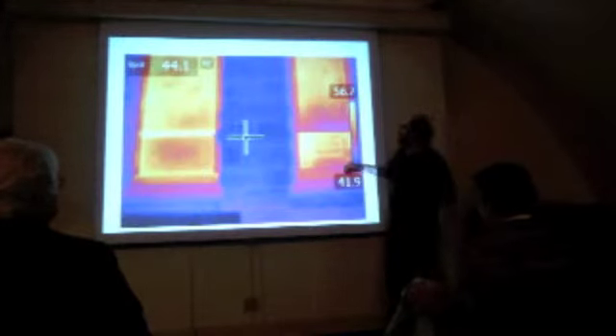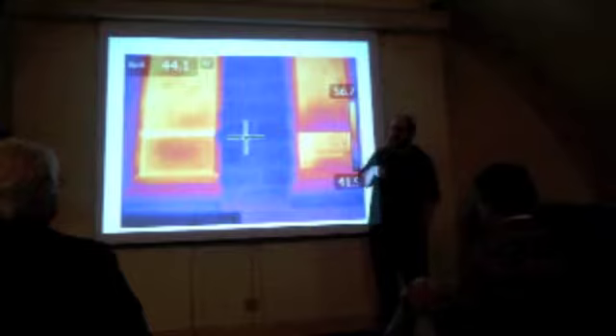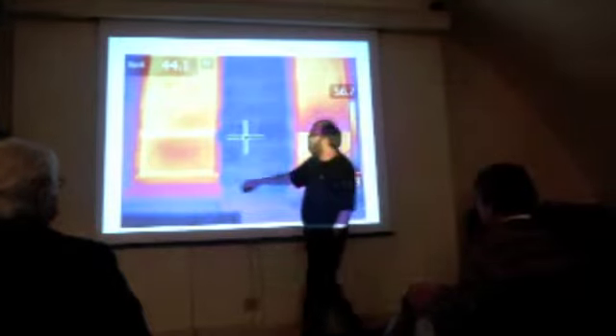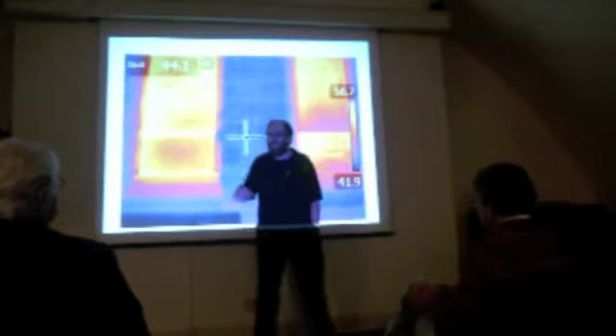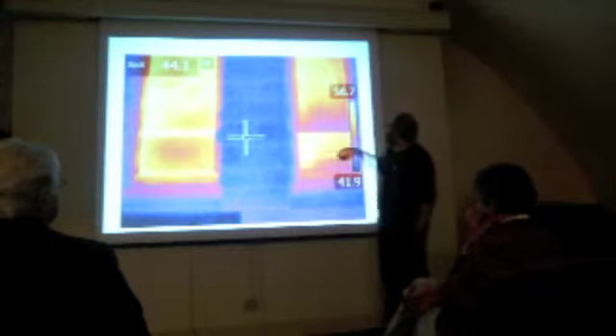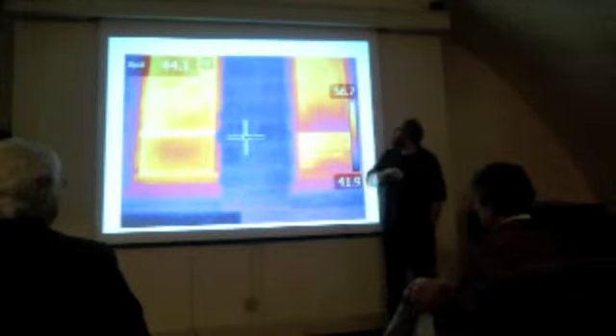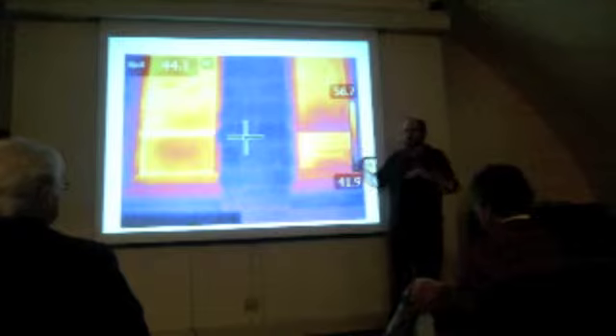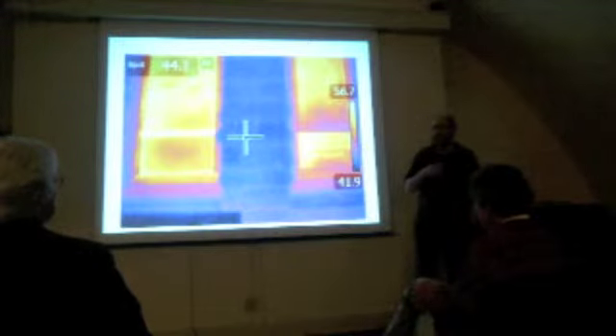And so the difference is a little less dramatic for the other ones, but again, the center window is the one directly above the heating element, and you can see that the outside panes of glass are going to be a little bit cooler for that one. But this would be something to look at. It may even be just a question of the way that air is directed that comes out, to find a way to direct it away from the windows rather than to allow it to loft straight up into those windows.